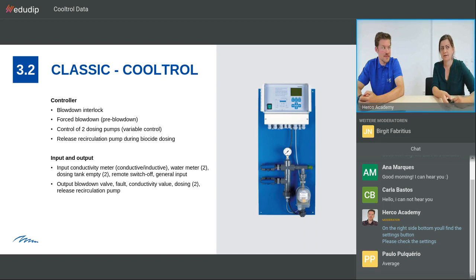The hardness related chemical. We have more inputs and outputs here already. So we have the input from the conductivity meter, which can be conductive or inductive. We have the inputs from the two water meters on the makeup water line and on the blowdown line. We have signals from the dosing tanks of these two, a remote switch off of the plant from the central system of the client, let's say, and a general input value.